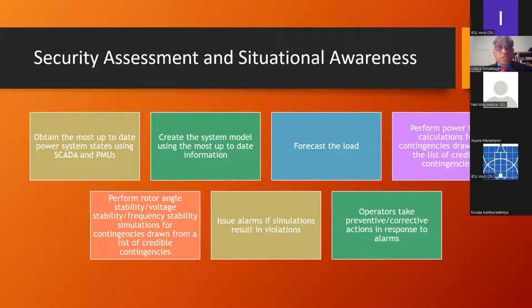In particular for voltage stability, sometimes we don't do the time domain simulation. We calculate indices to see how close we are to a voltage collapse situation. Are we at a safe distance from that? So based on all these simulations and computations happening behind the scenes, the operator gets alarms if there are any warning signs. If not, nothing comes. And if there are alarms, operators take preventive or corrective actions to respond to this.